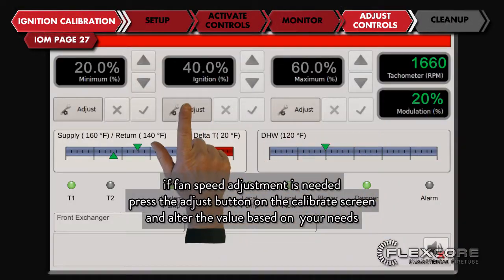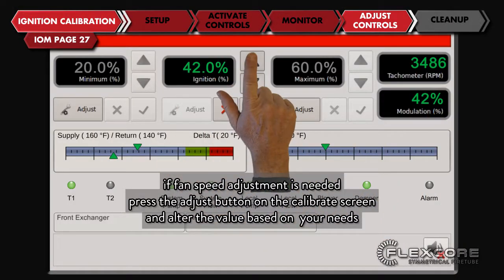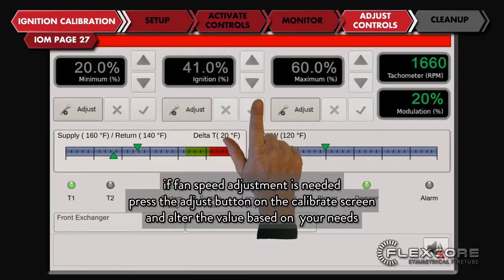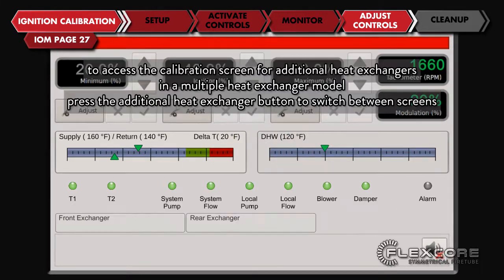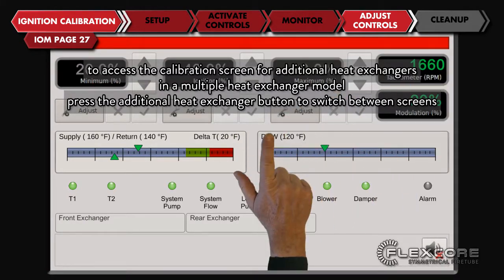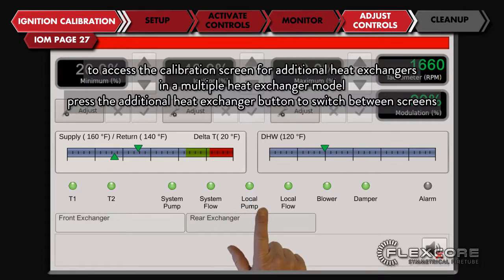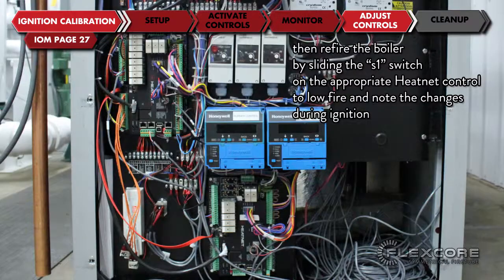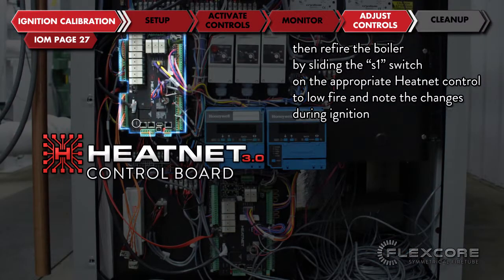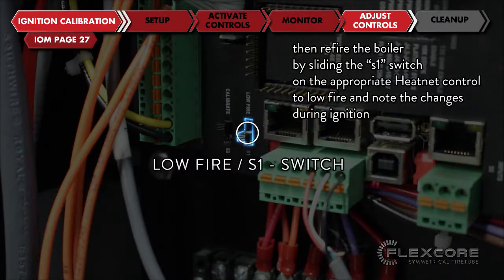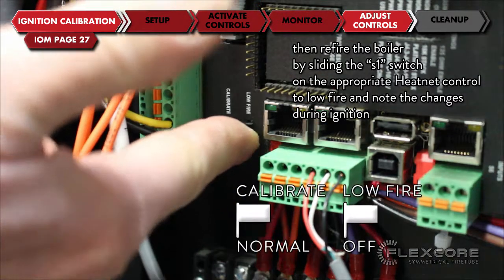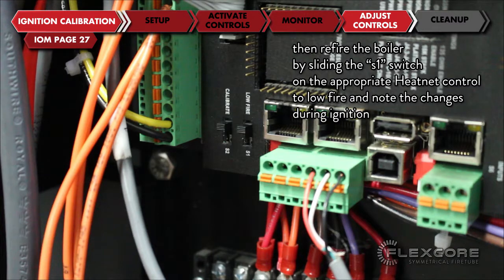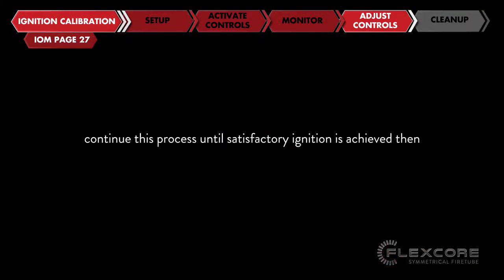If fan speed adjustment is needed, press the adjust button on the calibrate screen to alter the value based on your needs. To access the calibration screen for additional heat exchangers in a multiple heat exchanger model, press the additional heat exchanger button to switch between screens. Then, refire the boiler by sliding the S1 switch on the appropriate heatnet control to low fire and note the changes during ignition. Continue this process until satisfactory ignition is achieved.